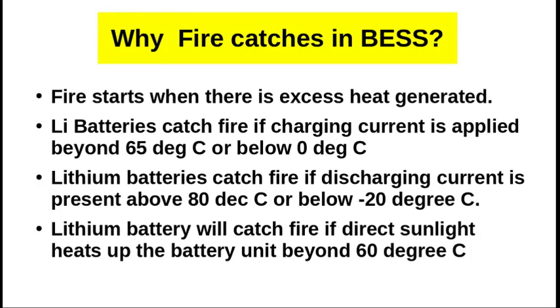Why does fire catch in BESS? The fire starts when there is excess heat generated inside the battery. Lithium batteries catch fire if the charging current is supplied beyond 65 degrees C or below 0 degrees C. Lithium batteries catch fire if discharging current is present above 80 degrees C or below minus 20 degrees C. The lithium battery will catch fire if direct sunlight heats up the battery unit beyond 60 degrees C.